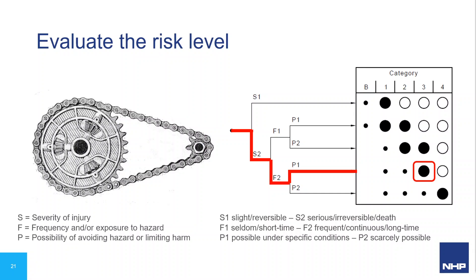We cannot use Category 1 or 2 in this scenario. But maybe we should take another look at the risk assessment. Perhaps we could reduce the frequency of exposure to the chain and sprocket. If we change the lubrication method — using an oil pump to automate it, or a better quality lubricant requiring less frequent application — we can reduce exposure enough to call it F1. This changes our path and we now end up with a safety system designed to Category 1 or 2.